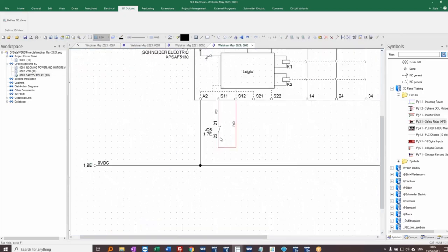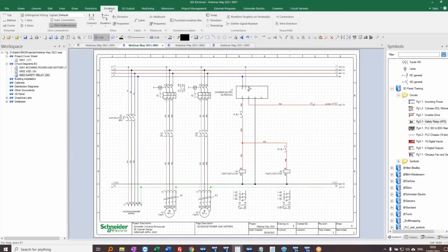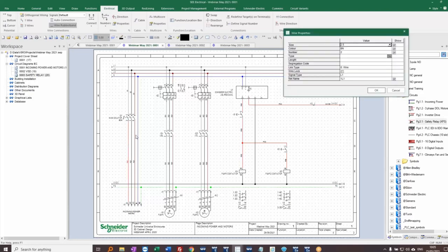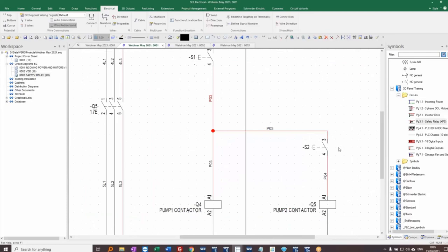With the advanced level, I can double-click and it takes me back to the corresponding contactor on the previous page. Within SEE Electrical, wiring information is important because it feeds through to the 3D panel. We have wire size, color, and the net name — a name for a whole group of wires at a certain potential. For example, P03 is the net name for a signal connecting between three different devices. In the 3D panel, we can optimize the connection order — for example, routing between push buttons on the door before running a single wire down to a contactor on the gear plate.